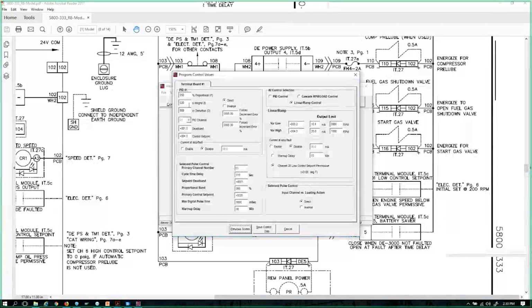But let's assume right now what we're going to do is control a suction control valve. Let's assume that the suction control valve is fail closed, meaning it takes 20 milliamps to fully open and 4 milliamps to fully close, through possibly an I to P converter. I to P stands for amperage to pressure converter. So just think of it as an electronic regulator.